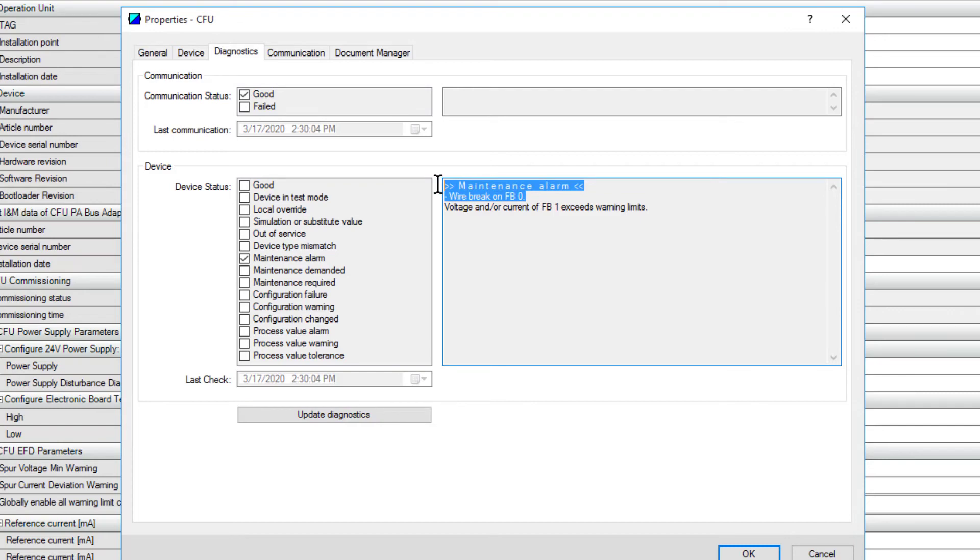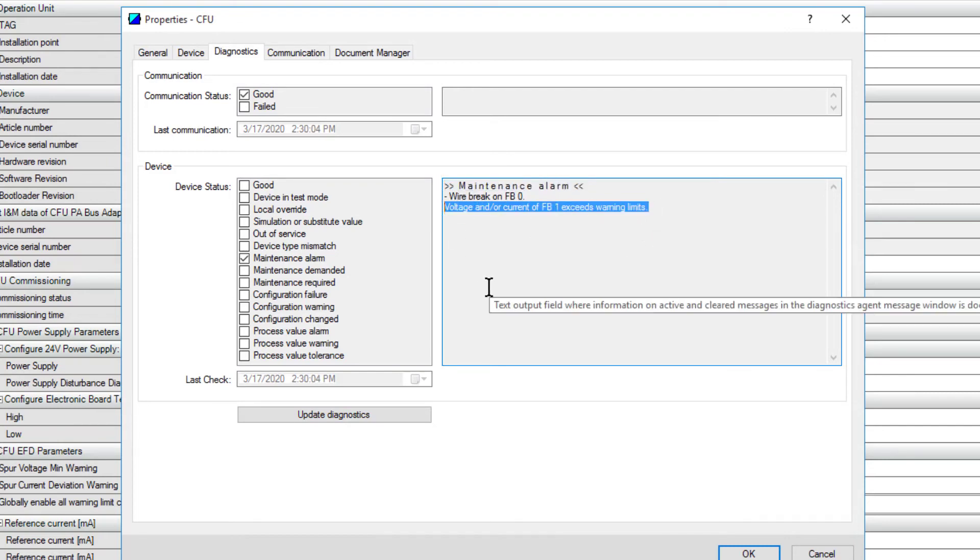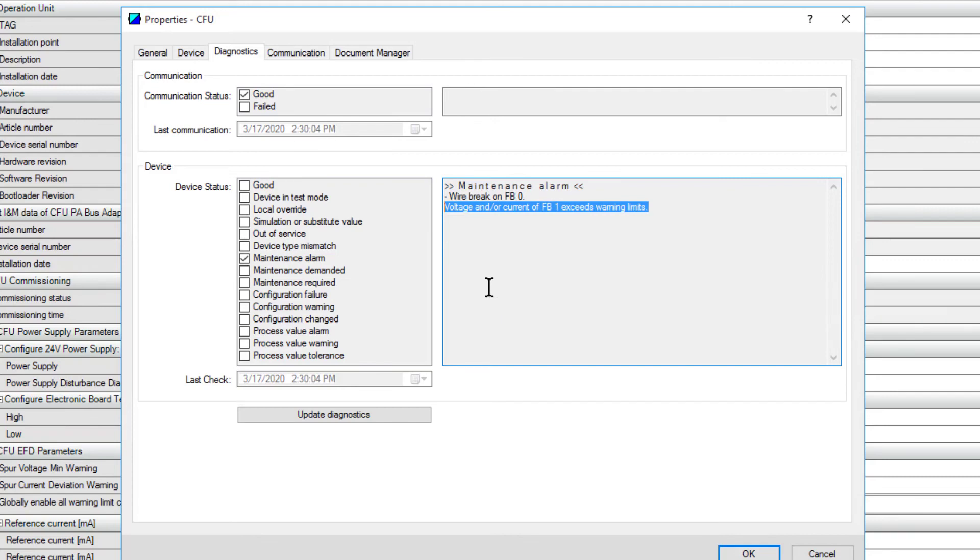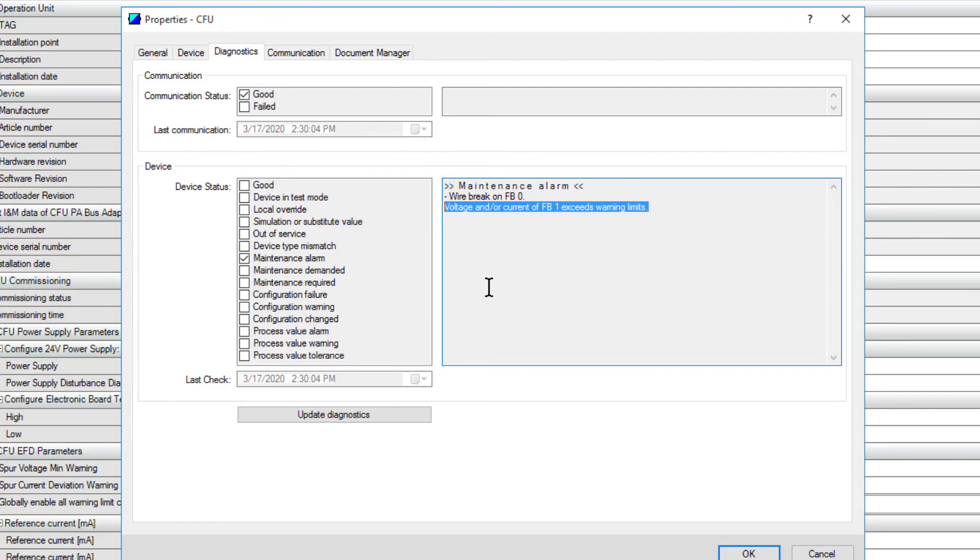I have a wire break on my first channel and the voltage on my second channel has been exceeded. When you set up the compact field unit, you have an option to monitor the current and voltage on that spur, which includes the instrument, or you can turn that off. It's a nice feature to have for water ingress problems. It hasn't affected my transmission of data. It's just given me a warning because this device draws a little bit more voltage. It's an ultrasonic sensor. It needs more power to excite the crystals.